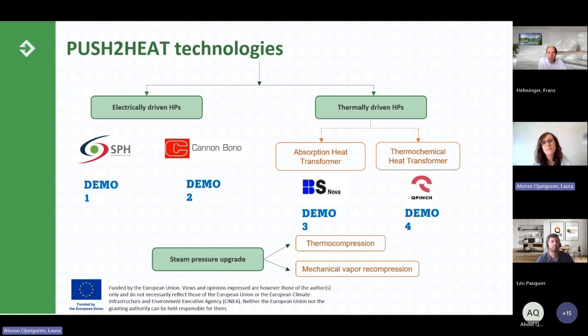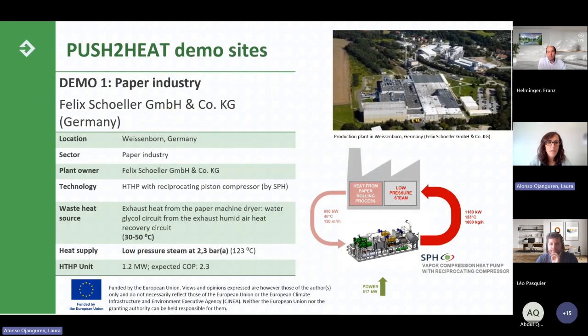And then we have, on the other hand, the thermally driven heat pumps. Among these kinds of heat pumps, we can differentiate between the absorption heat transformer by BS Nova, which will be tackled in Demo 3, and also the thermochemical heat transformer by Qpinch, which will be addressed in Demo 4. Okay, all these technologies will provide steam for the industry, and in certain cases, we are using, combined with the heat pumps themselves, external steam pressure upgrade systems, such as thermocompressors or mechanical vapor compression systems. Okay. And now let's go to the demo sites themselves.